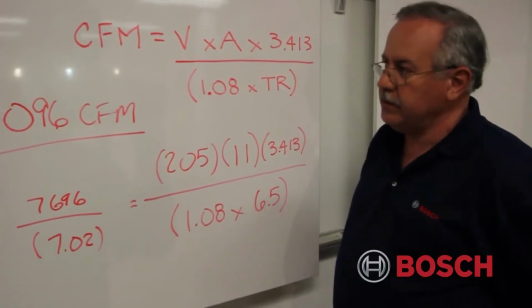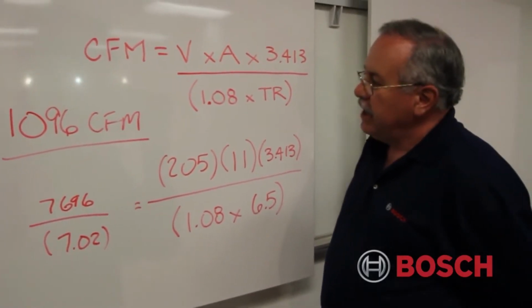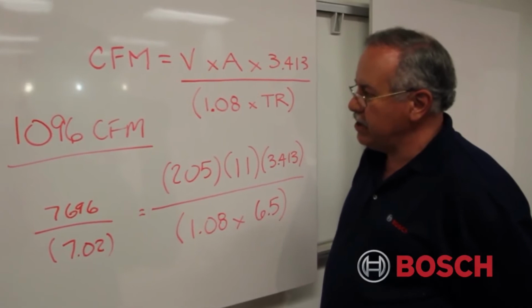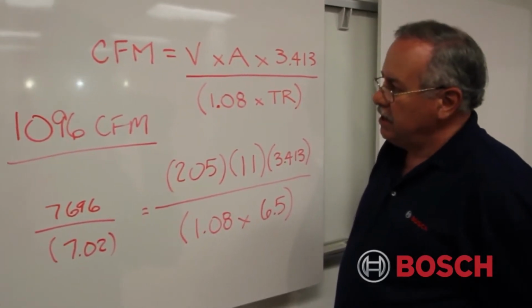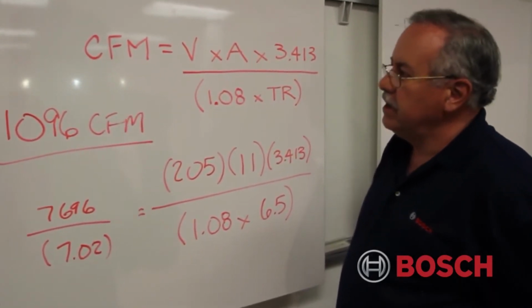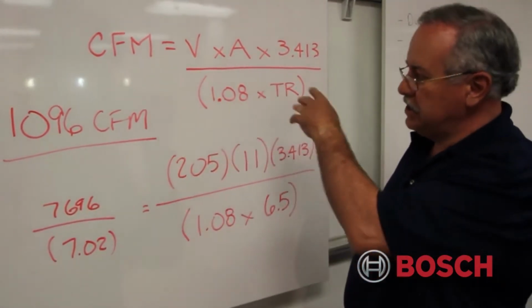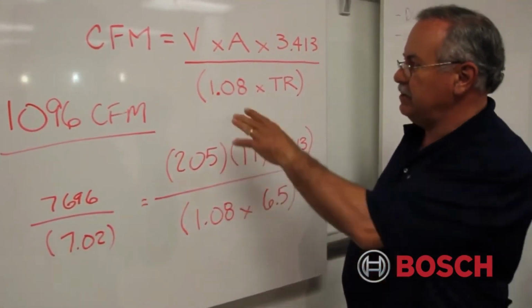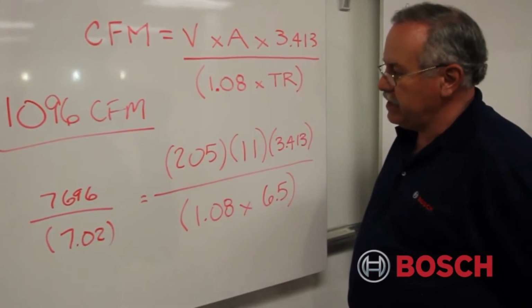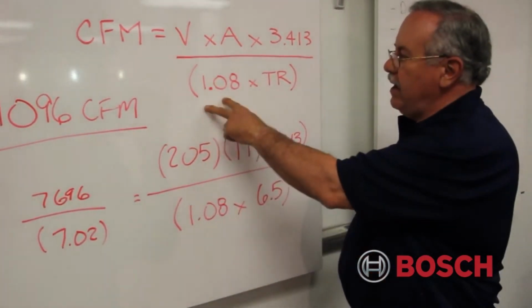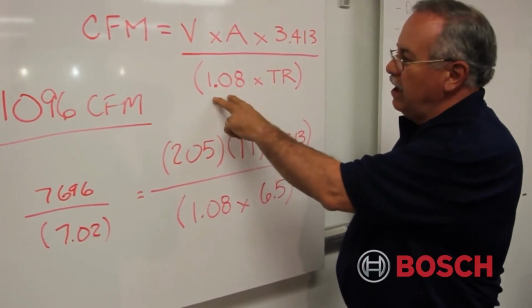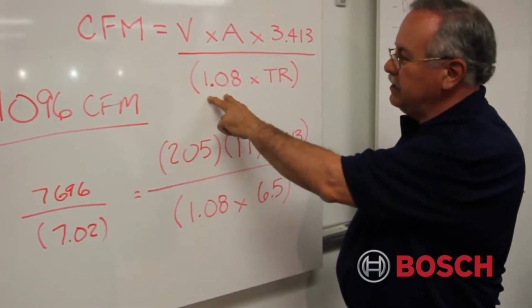Okay, so now that we have measured our voltage drop at the disconnect and the amperage draw of our heater energized, and we've taken the delta T or temperature rise across the heaters with acceptable diagnostic tools, we use a simple formula, which is CFM is equal to volts times amps times the conversion of 3.413 BTUs per watt, divided by the factors we're going to multiply together in the denominator, 1.08, that considers the properties of air, and the temperature rise that we saw.